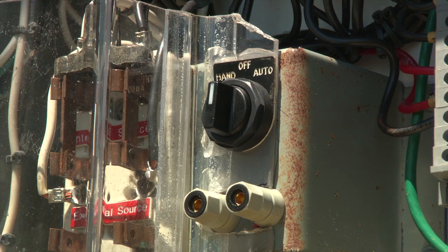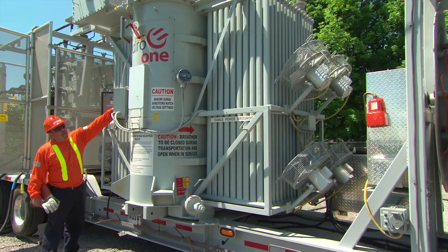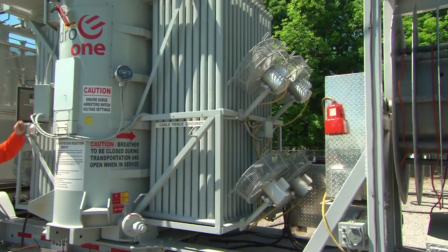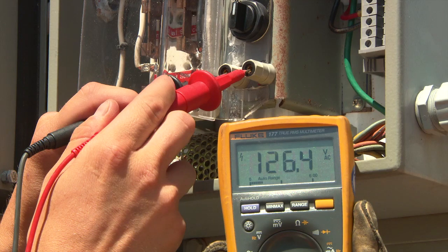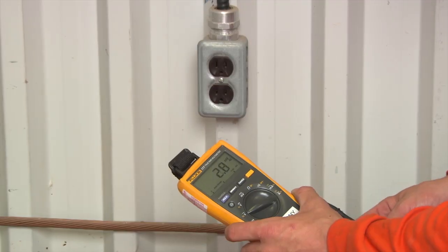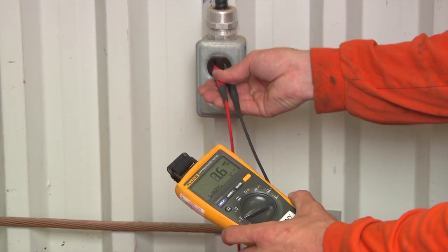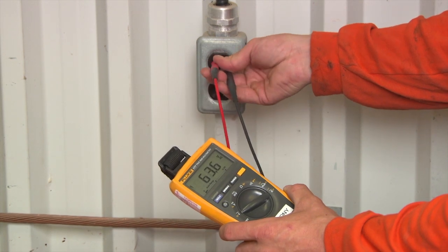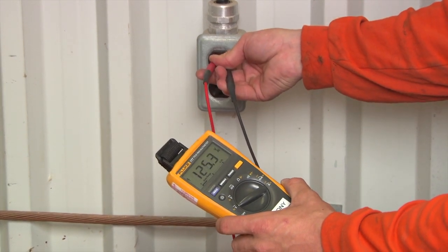Using the auto hand controller located in the transformer mech box, turn the fans to hand and ensure they are functioning properly. Then place the fans back to auto. Using a multimeter, test the secondary voltage of the MUS and the DS to ensure that they are as close as possible. Ideally, the MUS should be higher than the DS by less than 5%.